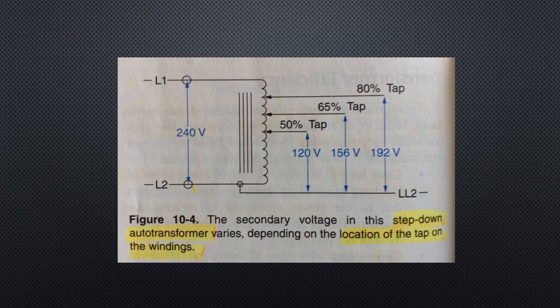Transformers can also be classified by their windings. In an isolation transformer, the primary and secondary windings are physically separate and independent. In an auto transformer, there is only one winding shared by the primary and secondary circuits. See figure 10-4. Auto transformers are used when voltage reduction is needed, such as starting AC motors. Though economical to manufacture and very efficient, auto transformers are limited in application due to their low voltage ratios.